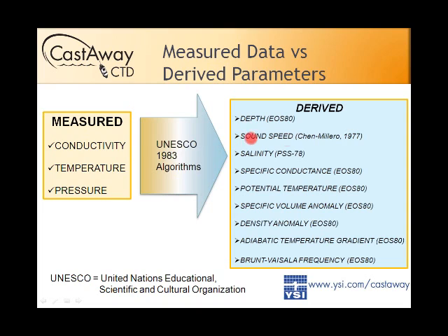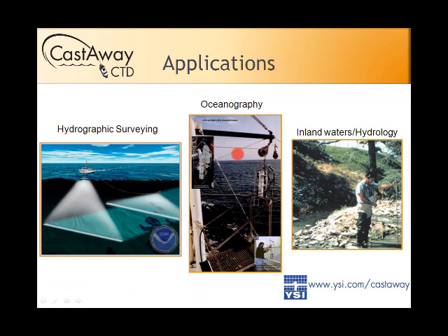We get a lot of questions about the sound speed algorithm — we use the Chen-Millero formula, the most commonly accepted one. Salinity is a derived parameter from the conductivity measurement, as is depth. We record the raw data; these are derived parameters output through the software, but users can clearly output data in raw form and run their own calculations if they prefer a different sound speed equation.